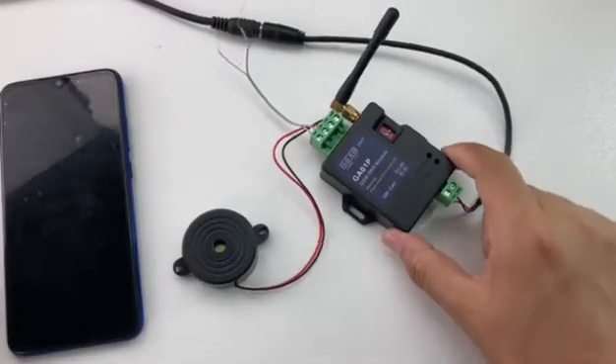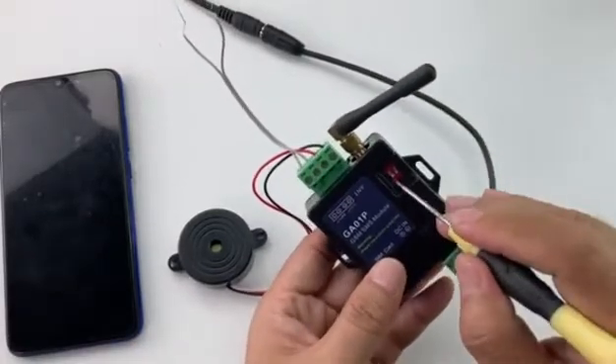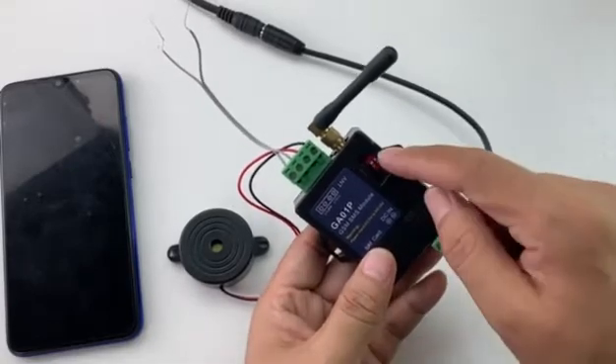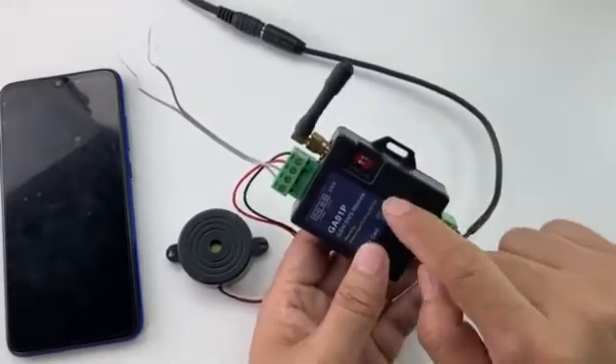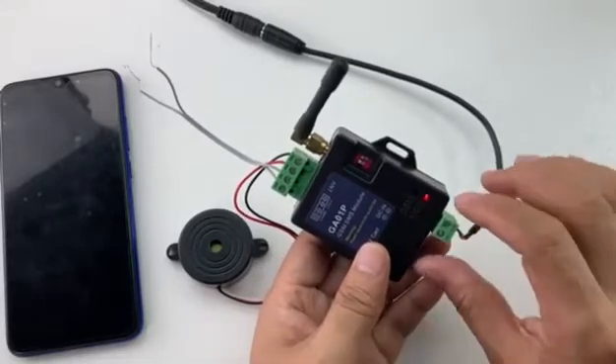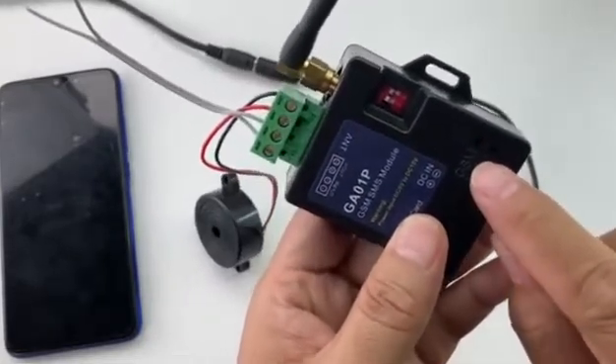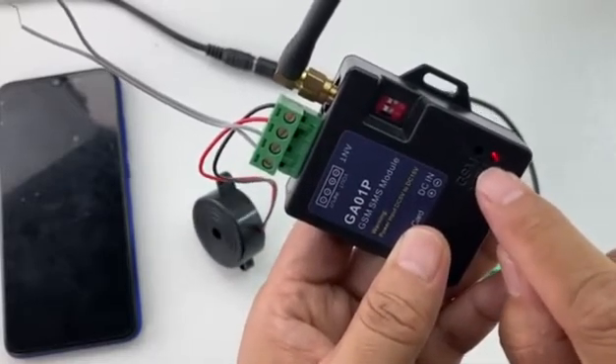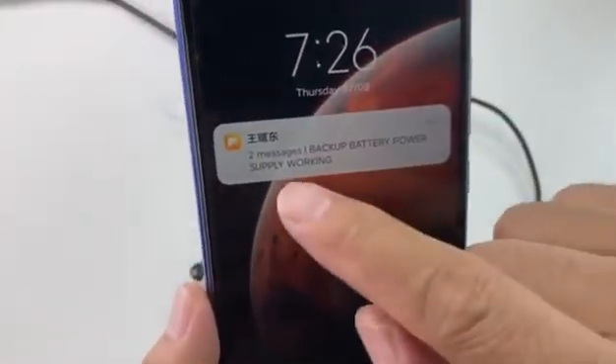Now we start to test the power failure alarm. Firstly, we need to move the DIP switch all to the on side. When at the on side, if we disconnect the power input, the battery will keep the device powered on and also send an alarm SMS. We disconnect the power — the device is still powered on with the battery. Some seconds later it starts to send the alarm SMS.